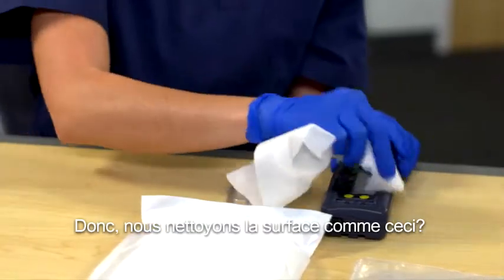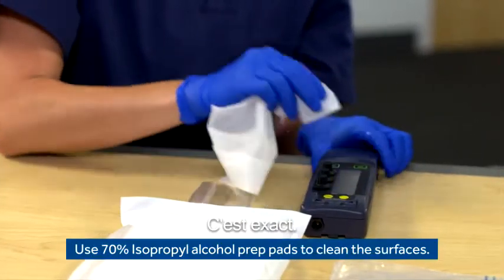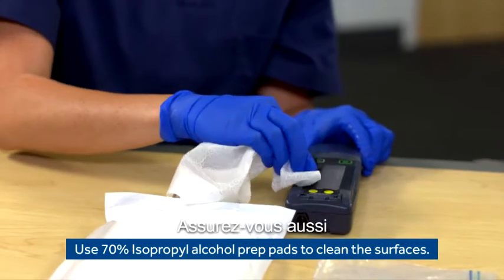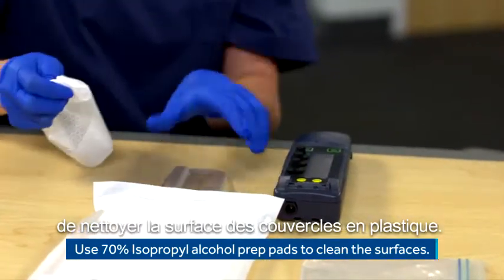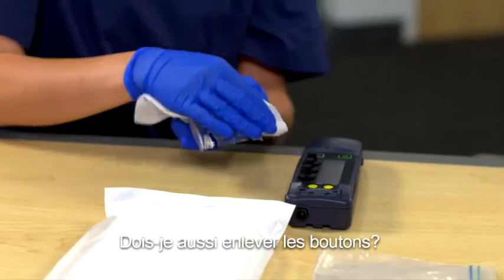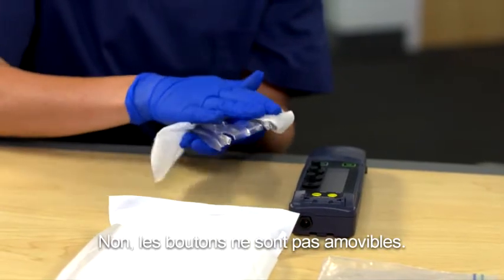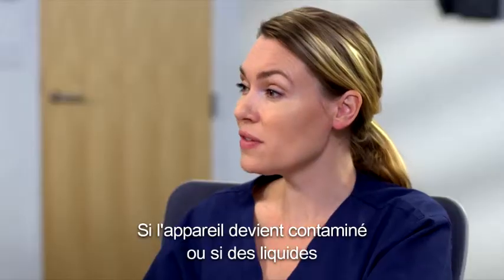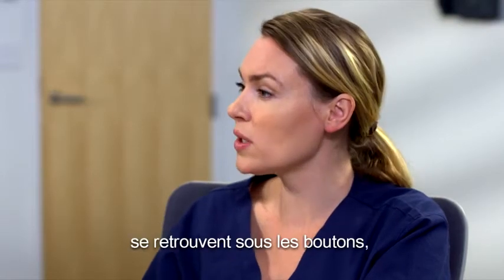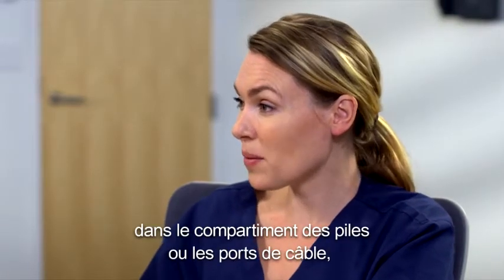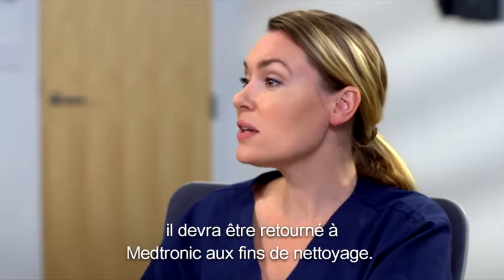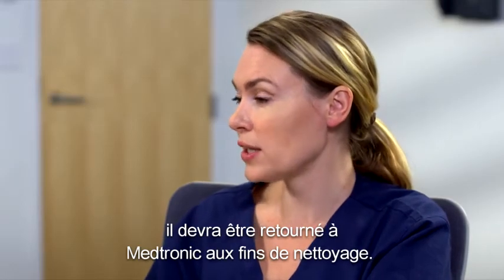So we clean the surface just like this? Yep, correct. So be sure to get the surfaces of the plastic covers as well. Okay. Should I also remove the knobs? Nope, the knobs are not removable. If the device gets contaminated or fluid gets under the knobs into the battery compartment or the cable ports, it'll need to be returned to Medtronic for cleaning.